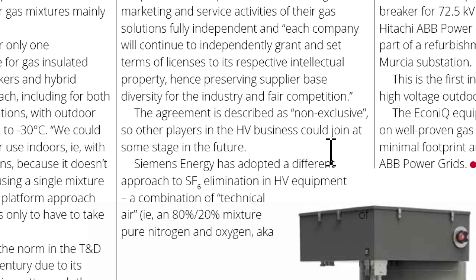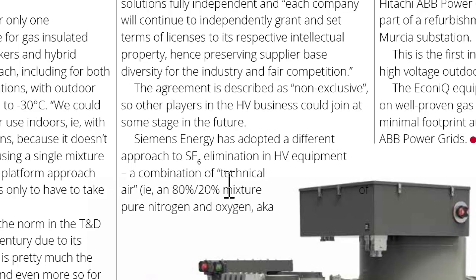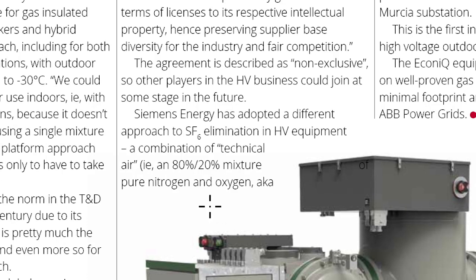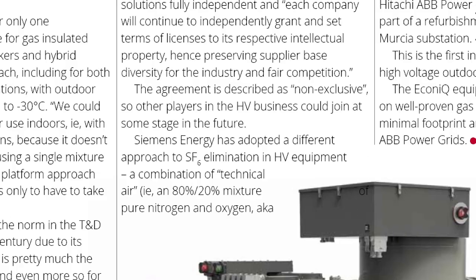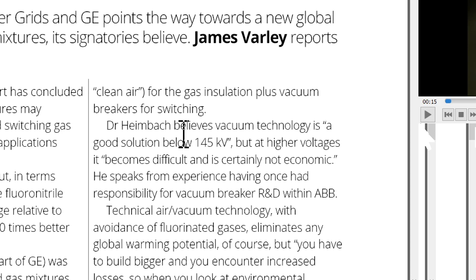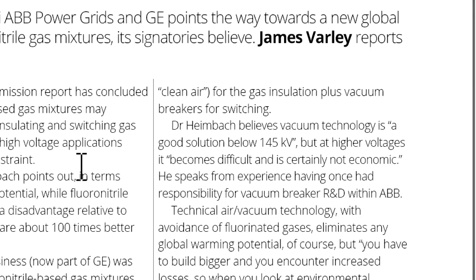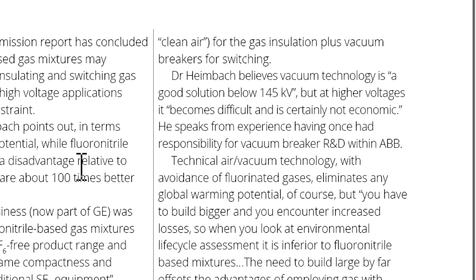Siemens Energy has adopted a different approach to SF6 elimination in HV equipment: a combination of technical air, for example an 80-20% mixture of pure nitrogen and oxygen, aka clean air, for the gas insulation, plus vacuum breakers for switching. Dr. Heimbach believes vacuum technology is a good solution below 145 kV, but at higher voltages it becomes difficult and is certainly not economic.